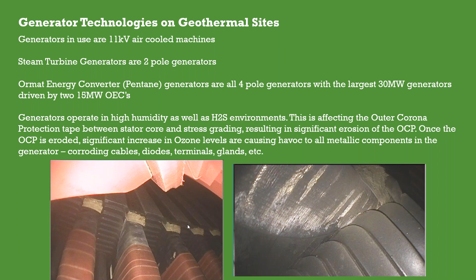And this machine is 4 years old. This is not an old machine. This is a 4-year-old machine that looks like this. So yes, this H2S environment is quite corrosive. And then the natural product of this high PD, or high partial discharge, is ozone. And ozone, again, is extremely corrosive. So anything inside this machine that's not protected by a corrosion resistant layer gets heavily corroded. All metal screws and copper cables and whatever is metallic and exposed just corrodes away. So yes, unfortunately, there's always a negative to the positive.